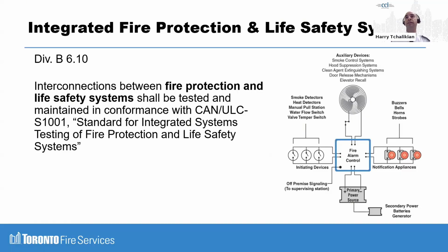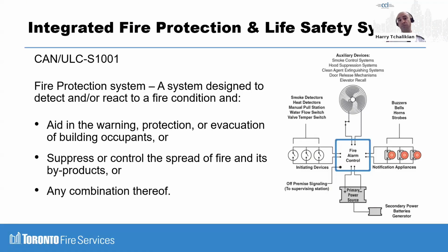So Division B 6.10, interconnections between fire protection and life safety systems shall be tested and maintained in conformance with CAN ULC S1001, standard for the integrated systems testing of fire protection and life safety systems. The two systems as defined by the standard, you have fire protection system, a system designed to detect and or react to a fire condition and aid in the warning, protection, or evacuation of building occupants, or suppress or control the spread of fire and its products, or any combination thereof.